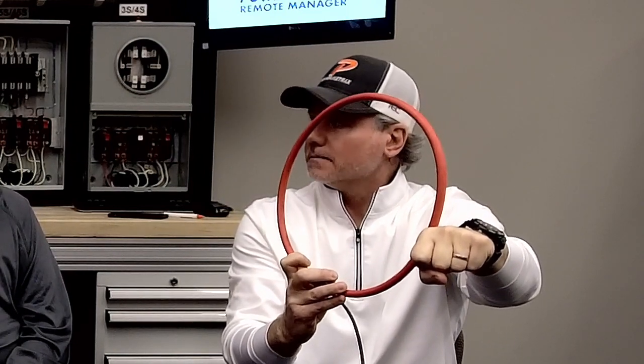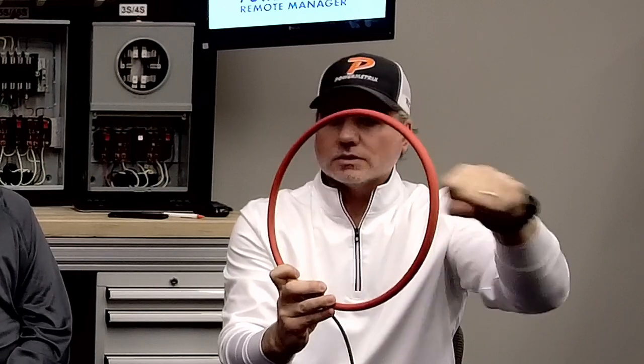The other big thing to know when you're using a Rogowski coil is on the outside, if that touches a voltage-carrying conductor, you'll get a worse reading. So it's about where it is in the window. We want to be up here now. We want to make sure it's perpendicular, like John said. We want to stay as far away from that as possible. We want to make sure there's not another conductor banging into this. Now, obviously, you can't make all those happen every single time, depending on what site you're on. You just have to do the best you can.